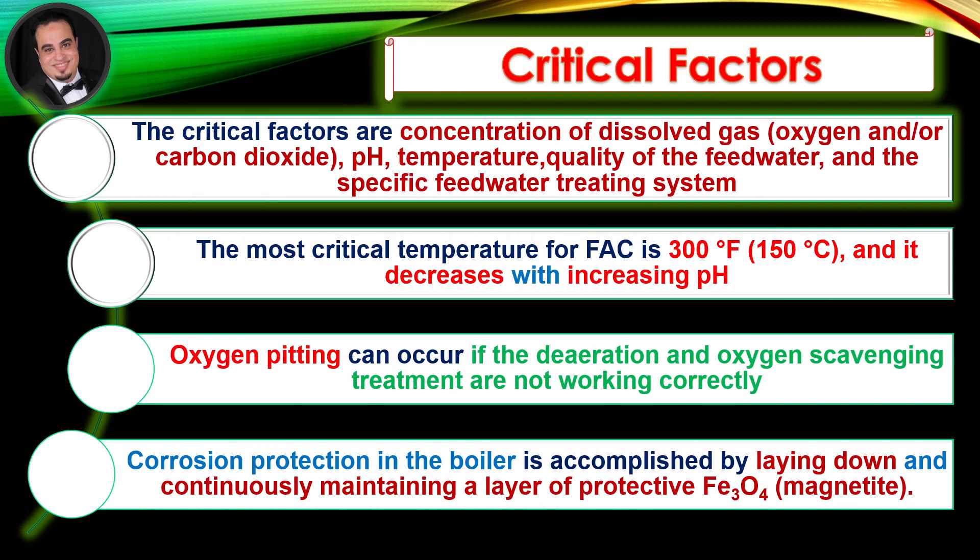Critical factors. The critical factors are concentration of dissolved gas — oxygen and/or carbon dioxide — pH, temperature, quality of the feed water, and the specific feed water treating system. The most critical temperature for flow accelerated corrosion is 300 degrees Fahrenheit, and it decreases with increasing pH. Oxygen pitting can occur if the de-aeration and oxygen scavenging treatment are not working correctly.